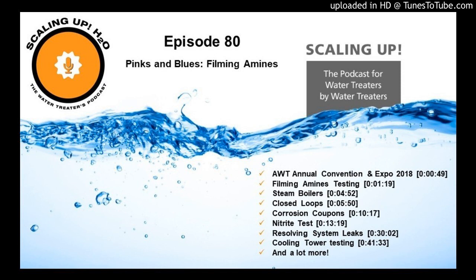Next thing we did is we didn't want to give any credit to our previous product to the Filming Amine product that we were testing. And we had an azole nitrite nitrate borate polymer blend that we were using for the past 6+ years. And again, getting really good results with that. So we wanted to go ahead and flush that out just to make sure that the results that we received were only due to the Filming Amine, not any other inhibitor that might be there.